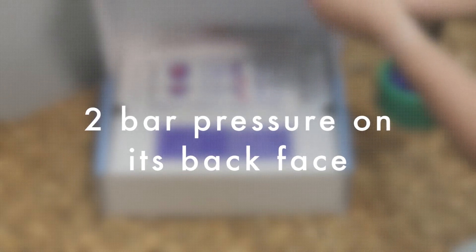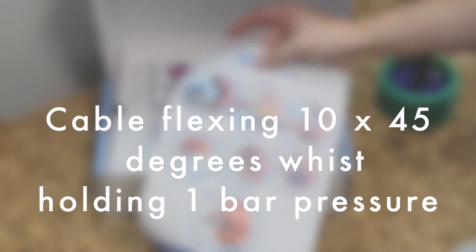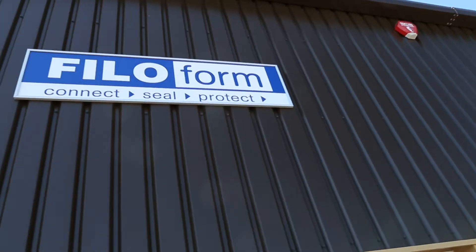FiloSeal Plus HD has been tested up to 2 bar pressure on its back face, 100kg pull force and cable flexing 10 times 45 degrees whilst holding 1 bar pressure.